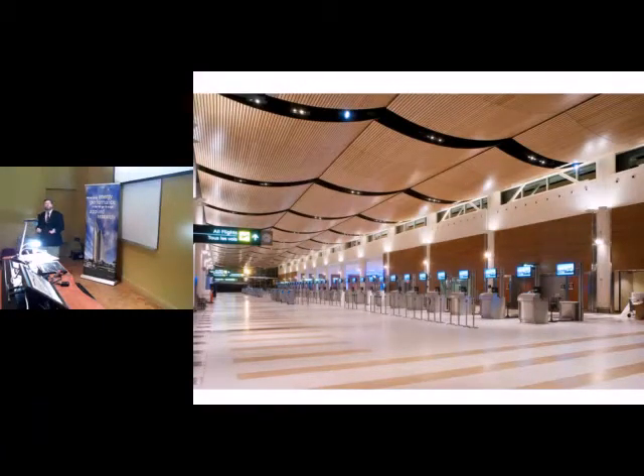We use that same effect in the departures hall. You'll notice a bunch of what we call eyeball diffusers along this strip, a series of jet diffusers that push out air at high velocity, up high, towards the occupied space of the departure hall. Each one is at a different angle, patterned to shoot close, medium, and far to get the air to move properly in the space. For a relatively small amount of fan energy, we push a stream of air about 150 feet out.